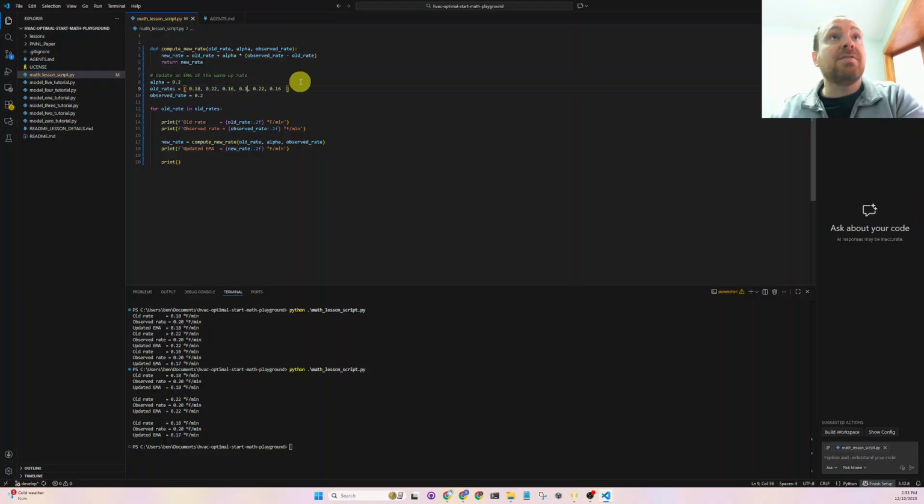We could even have an odd day, even some wild fluctuations in the data, and then it should actually help smooth out what's going on in the system. So basically, when we're talking about the Tridium's optimal start block, it only uses the previous day's performance. So with this, we'd be getting a little bit better performance by smoothing out this data with this alpha parameter.